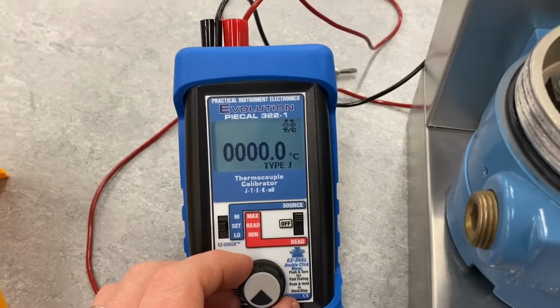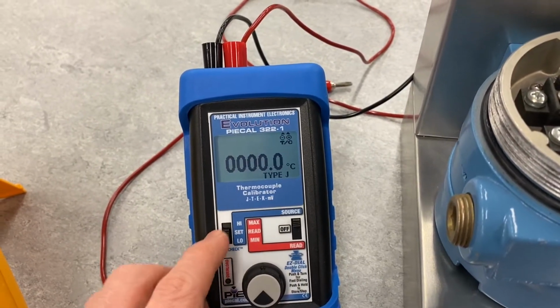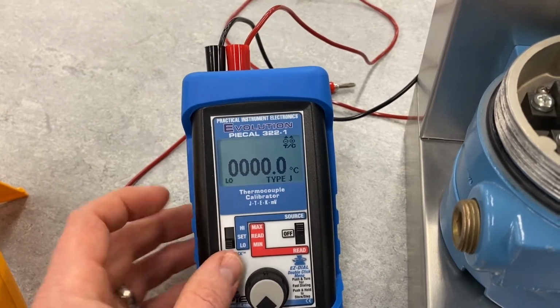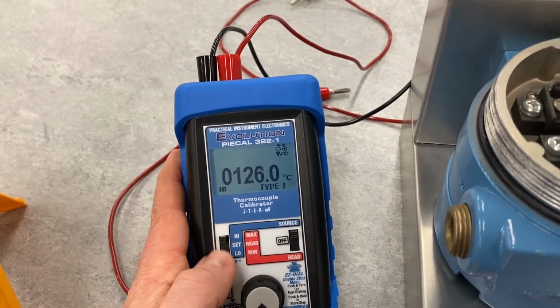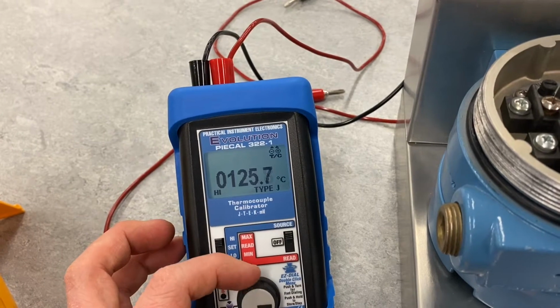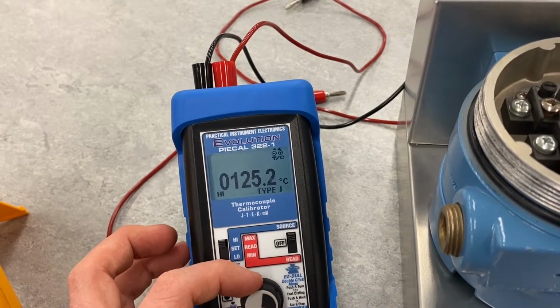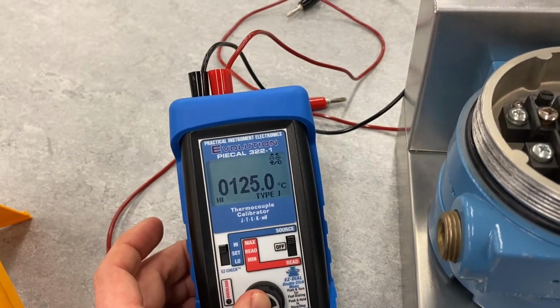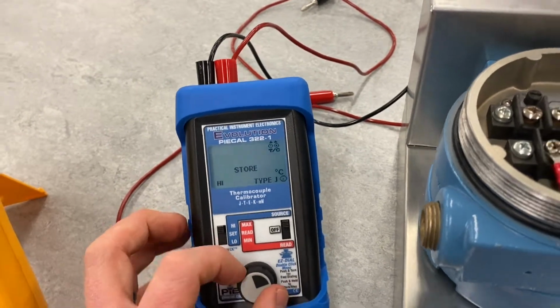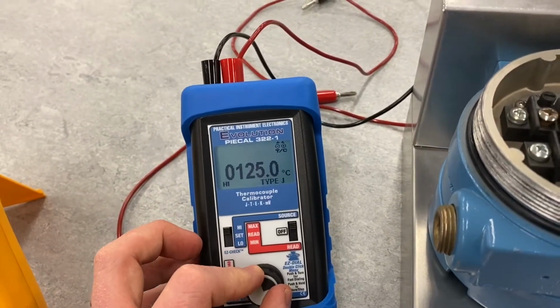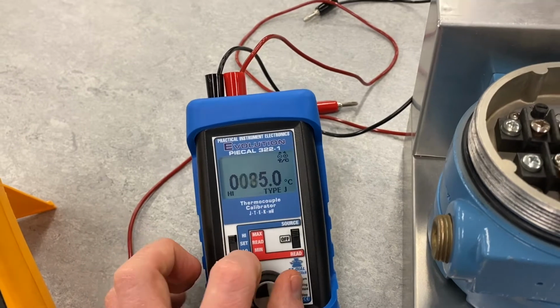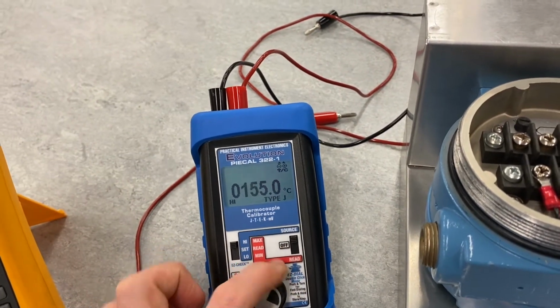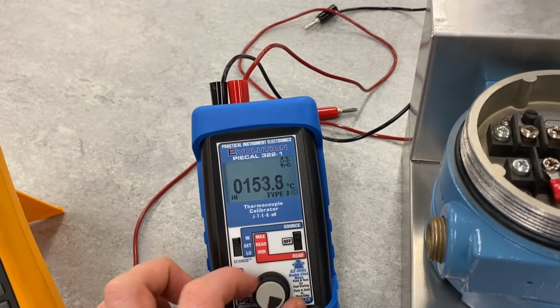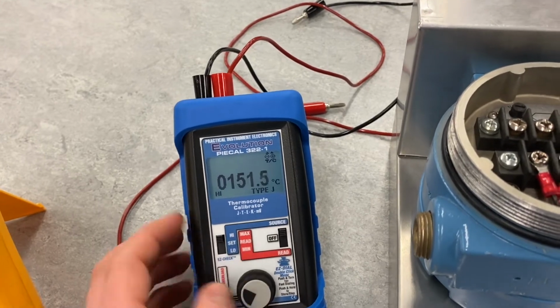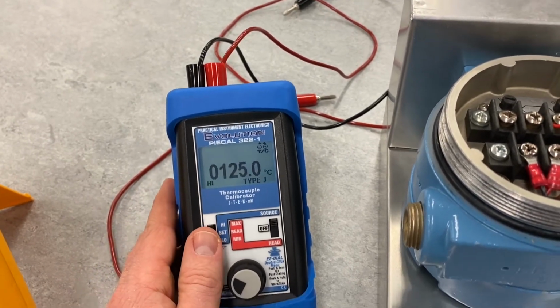So back over here, once we have the values that we want to calibrate this for, now we can go low for 0 degrees C and high for 126. We'll back that back to 125. Hold this down. It'll store the value. Another feature too, if we need to make big changes, if we push on the knob, it'll move around a lot more rather than not pushing on the knob. You can see it doesn't move the temperature as much. So let's set that to 125.